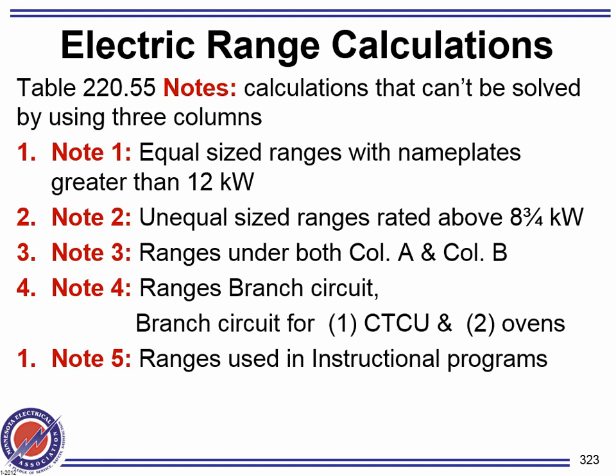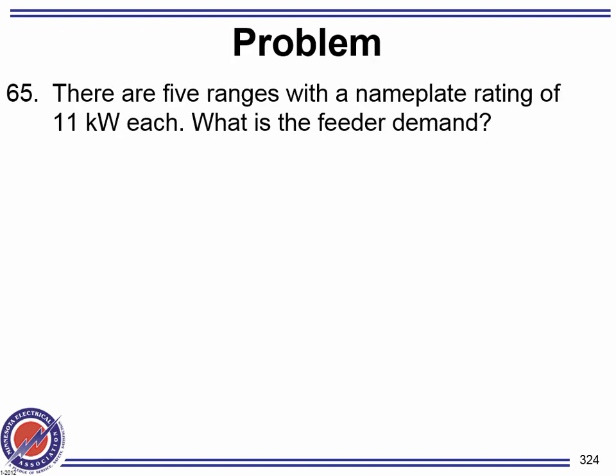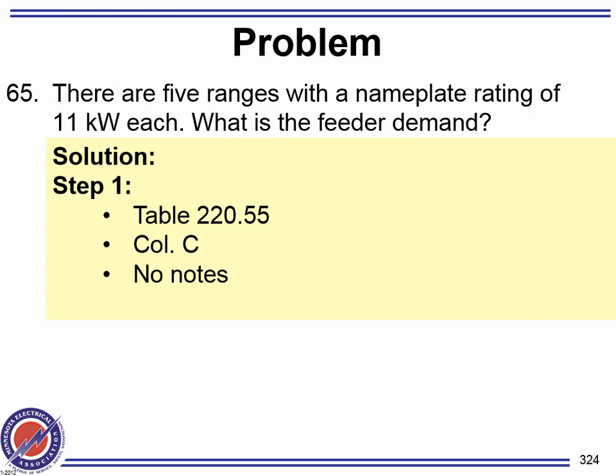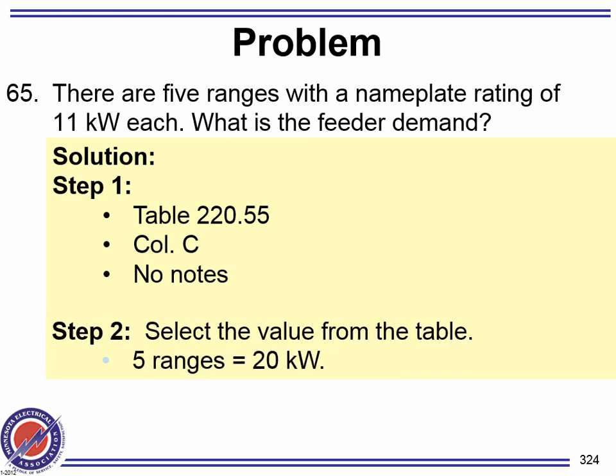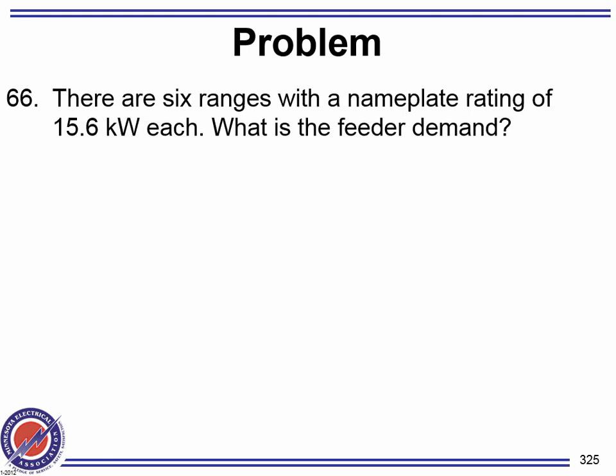Okay, here are the notes that we talked about, German. There are 5 ranges with a nameplate rating of 11 kW. From the get-go, 5 ranges. They're under C, all of them are under C, so the demand for 5 ranges is 20 kW. Ask yourself the question: is any one of them under A or B? Look at their size. They're 11. Is any one of them more than 12? You're done. That's it. You're not under A, you're not under B, and none of them is more than 12. You're done. That's it.